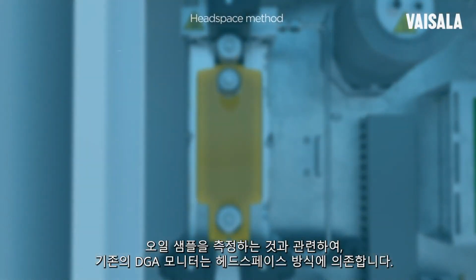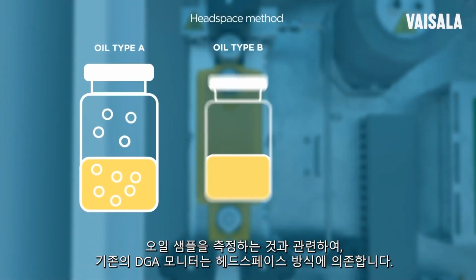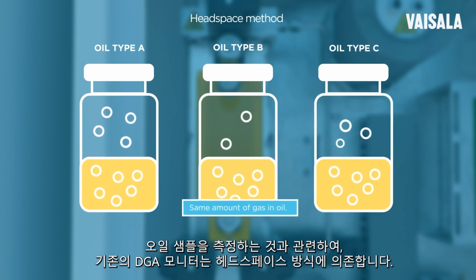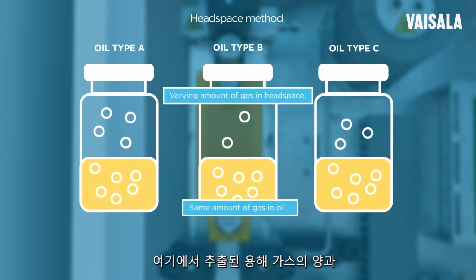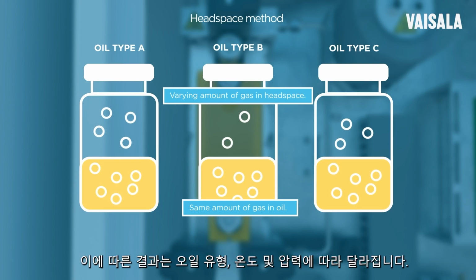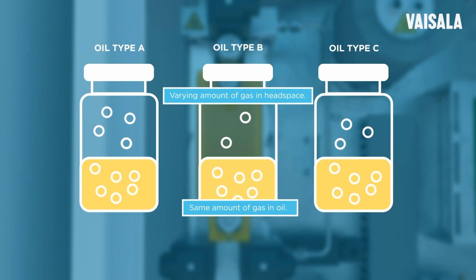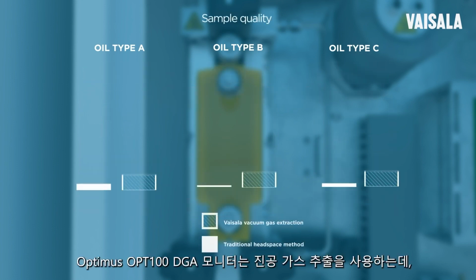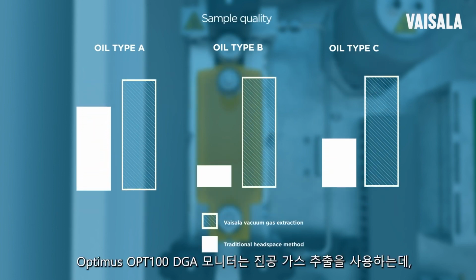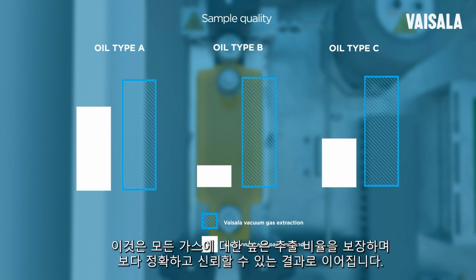When it comes to measuring oil samples, traditional DGA monitors rely on the headspace method, where the amount of dissolved gas that is extracted, and hence the result, varies with oil type, temperature, and pressure. The Optimus OPT100 DGA monitor uses vacuum gas extraction, which guarantees a high extraction proportion for all gases and leads to more accurate and reliable results.